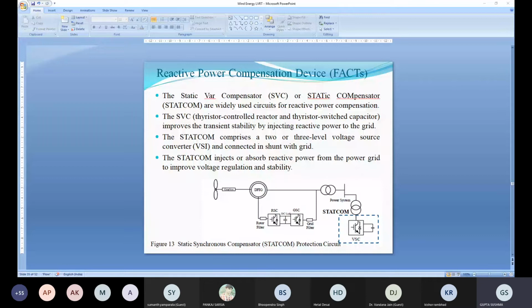StatCom is connected in shunt with the grid and provides reactive power if it is required. If there is a dip in grid voltage, StatCom will provide the energy to recover the grid voltage. Under normal operation, it takes active power from the grid and maintains the DC voltage. So StatCom can absorb or inject reactive power from the power grid to improve voltage regulation and stability.